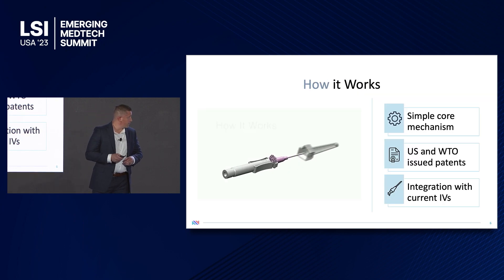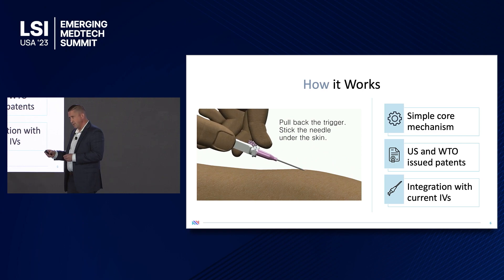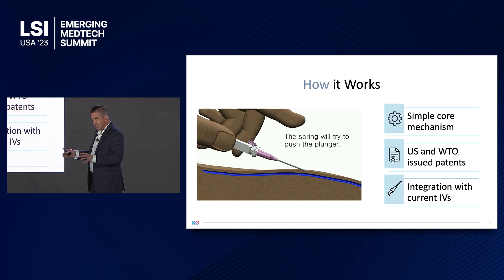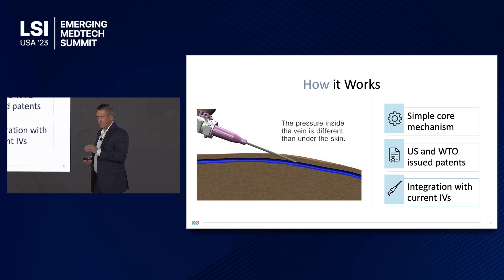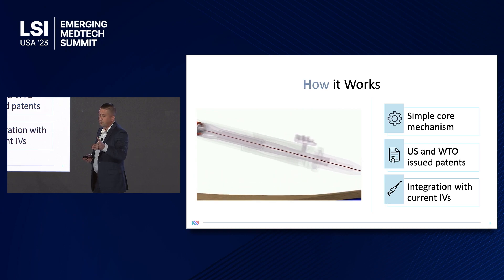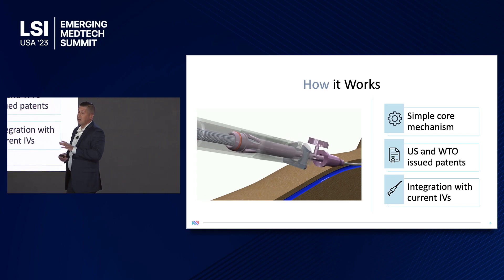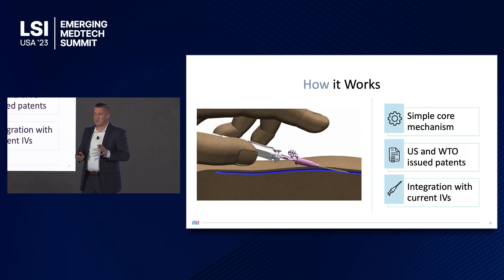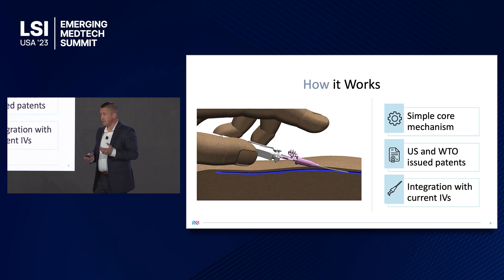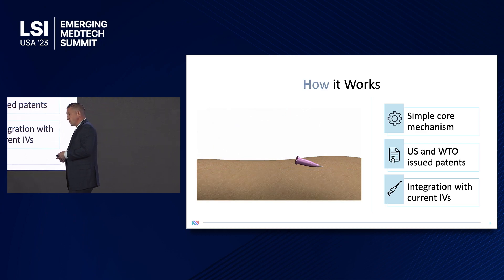Here's a short video on how it works. Before inserting the catheter, you press a button which activates a vacuum in the back of the housing. You release that once you're under the skin, and the skin creates a vacuum seal around the tip of the needle. You then advance the needle according to standard clinical technique, and once the tip enters the vein and senses the positive pressure in the vein, a little bit of blood is withdrawn into the needle, which breaks the vacuum in the back of the chamber. When that vacuum breaks, it pushes forward a spring, which advances the soft gel catheter into the vein. This all occurs in about 1/16th of a second, which is much faster than your normal human operator response time. The beauty of this is actually in the simplicity of that core mechanism, which is protected by several U.S. and world-issued patents.